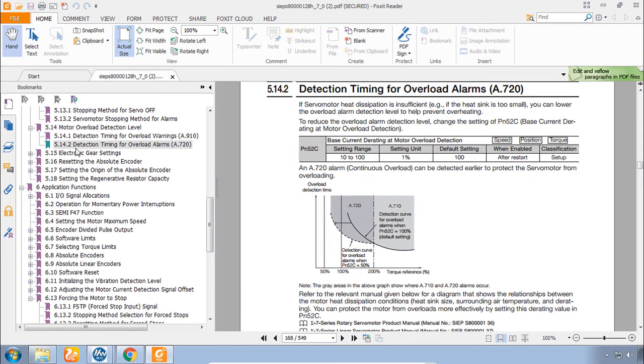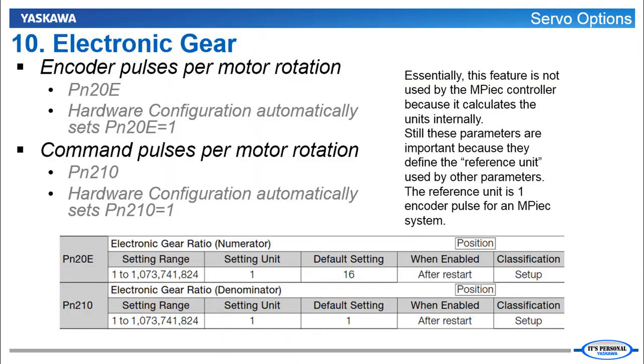Ok now the next topic in the manual is the electronic gear setting. I don't want to skip over this. However these parameters are controlled by the MPIEC controller. And they will always automatically be set both to one. Both parameters are a ratio. They're both set one to one. So this default of 16 does not apply to the MPIEC system. The MPIEC system commands the servo in units of encoder pulses. But these parameters exist for other controllers which may not have that capability. And instead they would be programmed in what's called the reference unit. So as it says here essentially this feature is not used by the MPIEC controller. Because that controller calculates the units internally. Still these parameters are important because they define this term reference unit used by other parameters and monitors that you'll see within the system. The reference unit is always one encoder pulse when you have an MPIEC system.